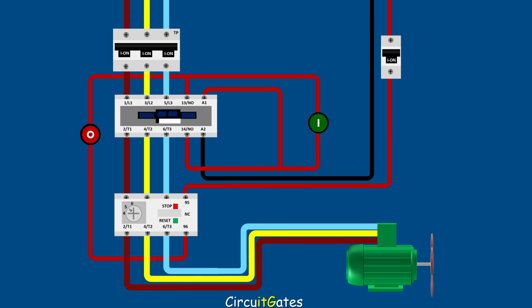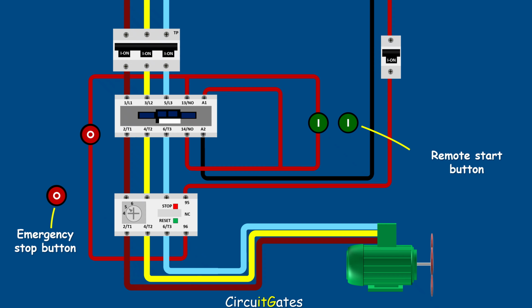The direct online starter circuit can have many switches, such as emergency stop buttons, limit switches, and more. But what is important is that if the switch is used to start the electric motor, it is a normal open contact switch and the switch is wired in parallel with the start button. If the added switch is used to stop the electric motor, it is a normal closed contact switch and the switch is wired in series with the stop button.